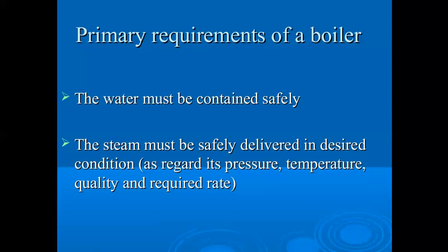And the evaporating capacity is 3000 kg per hour. The maximum capacity for a Cochran boiler is up to 4000 kg per hour. Its maximum operating pressure is 6.5 bar. If we exceed it, it is not a safe condition, so the pressure should be kept below the maximum.